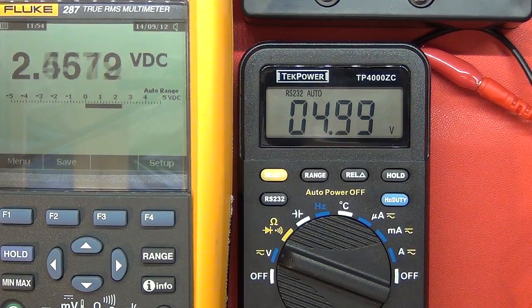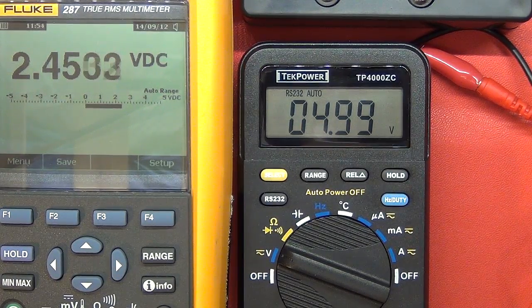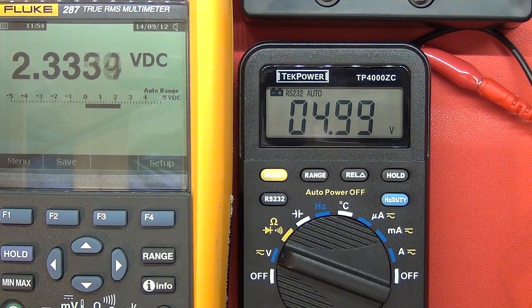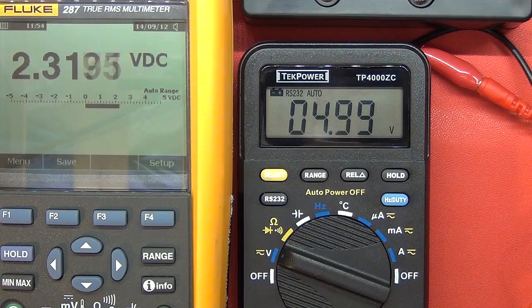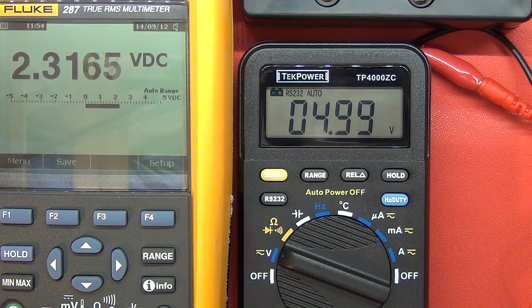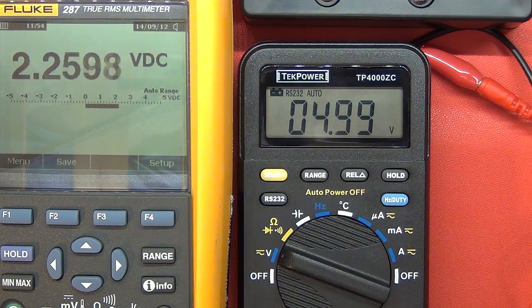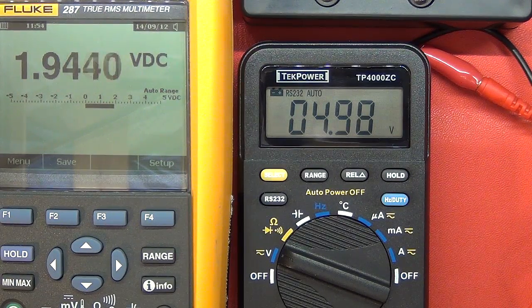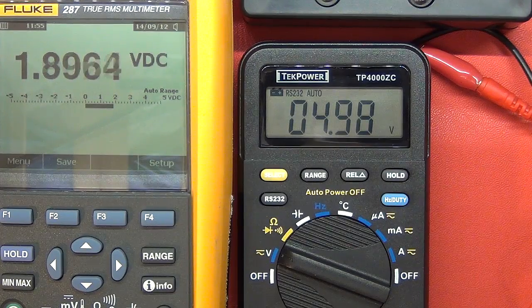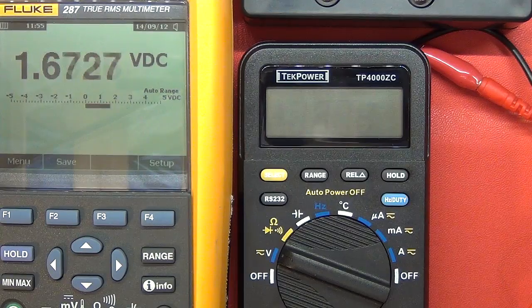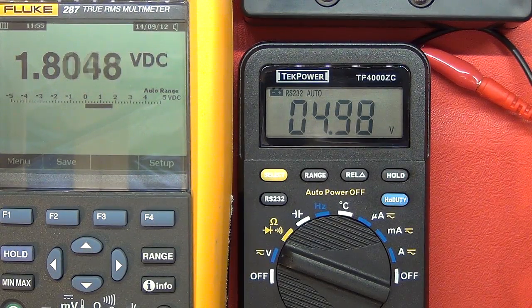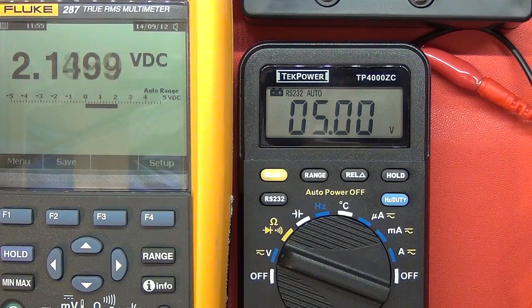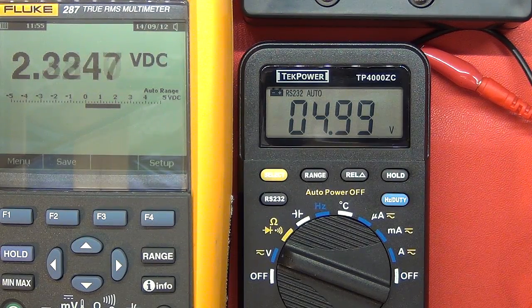So, let's just go down, down 2.4. Can't see anything coming on yet. Well, I suppose we're not quite there yet. Aha, there we go. We've got the annotation has come on saying the battery would be low, and it's maintained the measurement. We'll just go down a little bit further. See where it actually drifts. Still maintaining. Okay. And it probably switches off before it goes too inaccurate. So, you get a fair amount of warning about the battery warning prior to it actually going off. So, that's good.